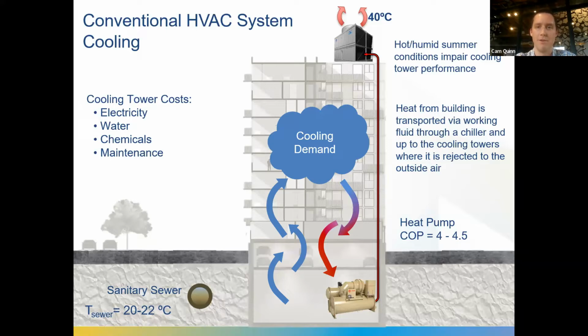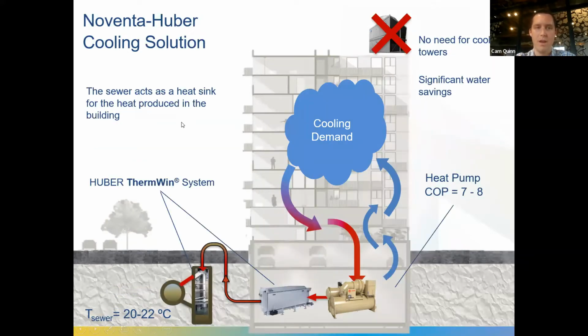And as those things go up, the efficiency of the chiller, or rather the system as a whole, is impacted. On top of that, there are our cooling tower operating costs: we have electricity, and a big one is water. We have an open loop system with the atmosphere, and we're constantly losing water from this system to the atmosphere. We have to make it up. It's important to keep the chemistry of the system in the right range, and because we're losing water and ultimately some chemicals, there are lots of chemical dosage requirements to maintain the water chemistry. And then there's maintenance.